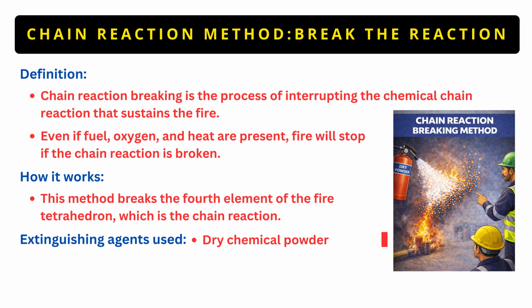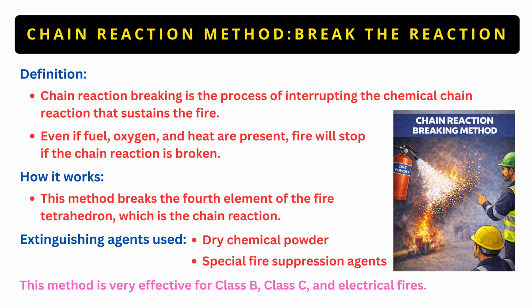Extinguishing agents used are dry chemical powder and special fire suppression agents. Now let us understand by this example. In gas fires or electrical fires, dry powder extinguishers are used to interrupt the chemical reactions at the molecular level, stopping the fire instantly. This method is very effective for class B, class C and electrical fires.